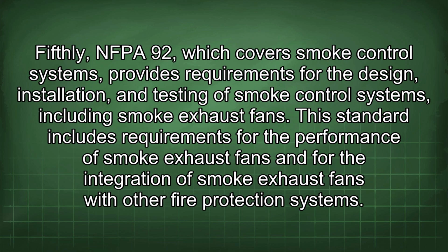Fifthly, NFPA 92, which covers smoke control systems, provides requirements for the design, installation, and testing of smoke control systems, including smoke exhaust fans. This standard includes requirements for the performance of smoke exhaust fans and for the integration of smoke exhaust fans with other fire protection systems.